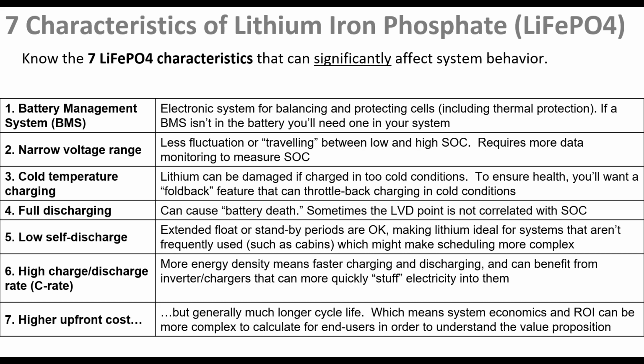So you can see they have a really broad range of environments they can work in. You want to be sure, as I said, that the LVD point is accurately correlated to the state of charge of the battery, because the battery will protect itself from that kind of chemical death if drained to 0%. The BMS will disconnect before that, so make sure your LVD setting on your charge controller is set above that value. That's usually a standard setting in Morningstar's products, at 20 or 30% remaining state of charge.